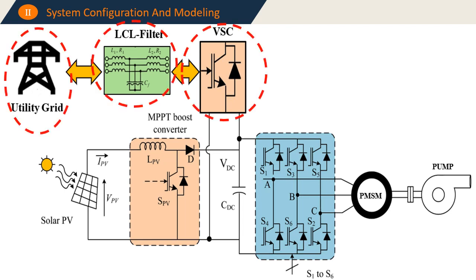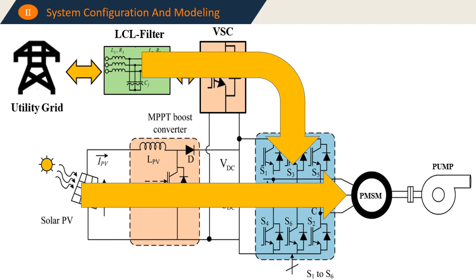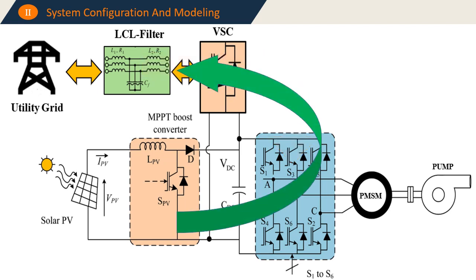The main elements of the photovoltaic water pumping system are the utility grid, an LCL filter, a voltage source converter with bi-directional power flow, a PV generator with a MPPT boost converter, and a voltage source inverter that drives the PMSM motor coupled to the centrifugal pump. This system has different operation modes: the PV generator can feed the pump alone; in case of low irradiance, the utility grid feeds the pump in parallel with the PV generator; or the pump can be supplied only from the utility grid. If pumping is not required, the PV generator can inject power to the grid.